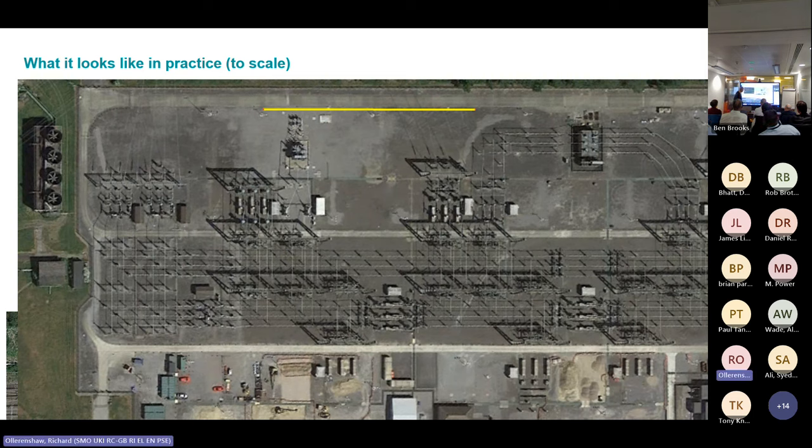But just skipping back to here, it's not just one of these. We then need the auto transformers every 10 to 12 kilometres along the railway, typically. So you have another one of these, a little bit smaller because they tend to use rationalised feeding. So you're off the order of that length of site every 10 to 12 kilometres, instead of one of our tin huts of East Coast practice every 15 to 20 kilometres. So more substations and a lot bigger.